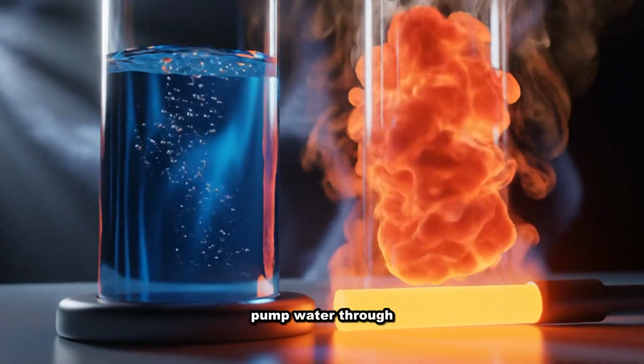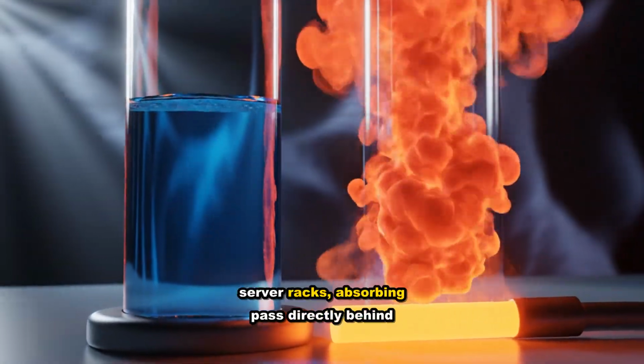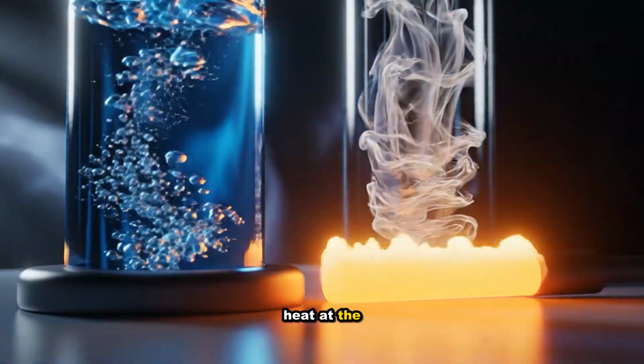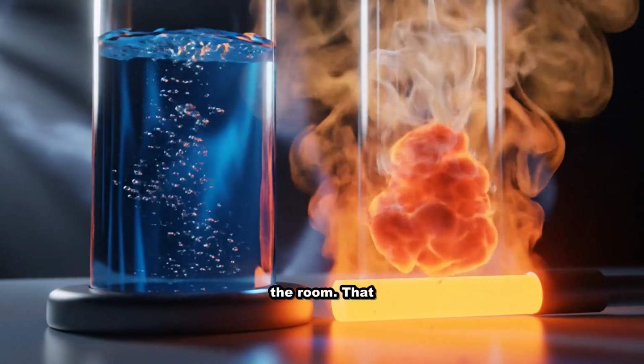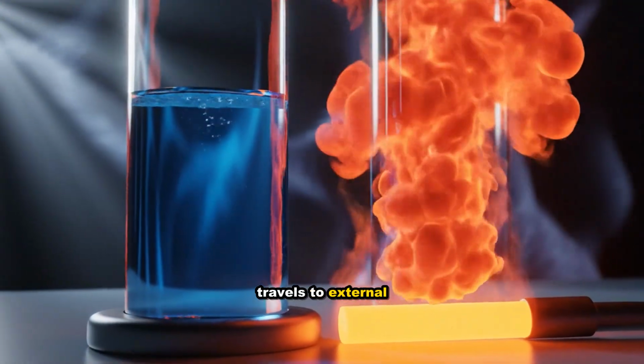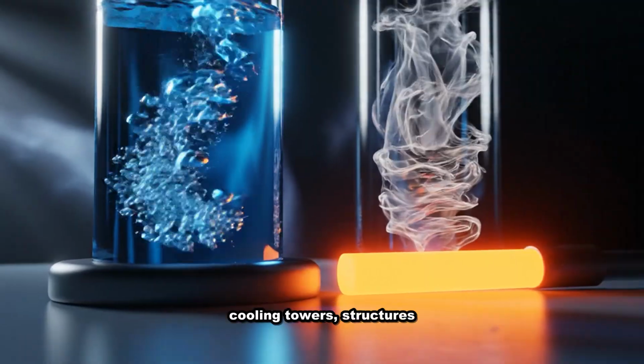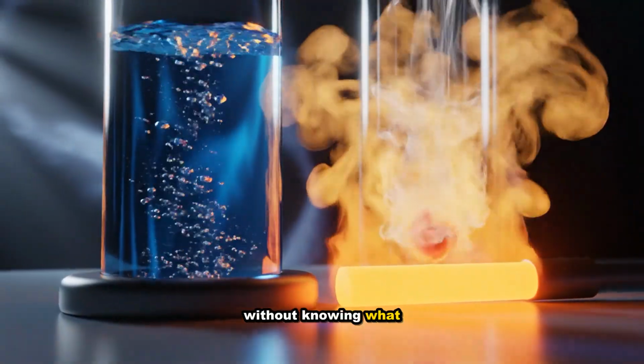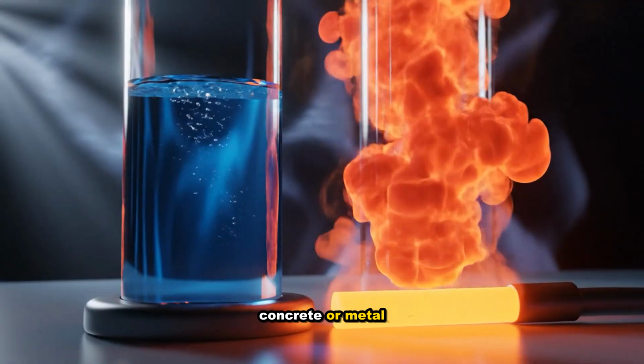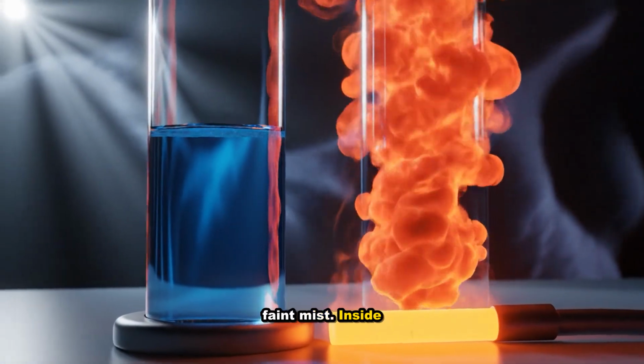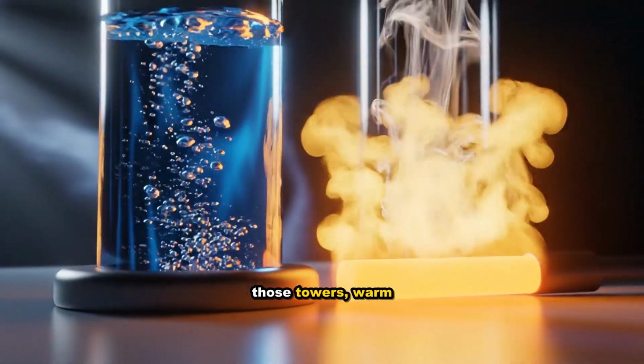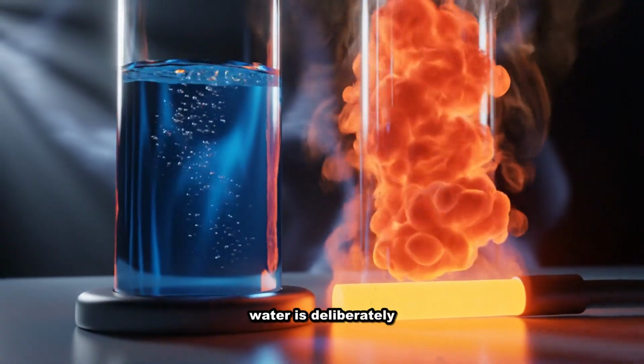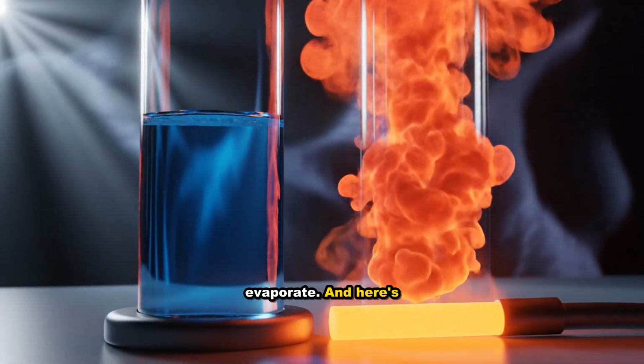Engineers pump water through cooling loops that pass directly behind server racks, absorbing heat at the source before it ever spreads into the room. That heated water then travels to external cooling towers, structures you've probably seen without knowing what they were: tall concrete or metal towers venting a faint mist. Inside those towers, warm water is deliberately exposed to air and allowed to evaporate.